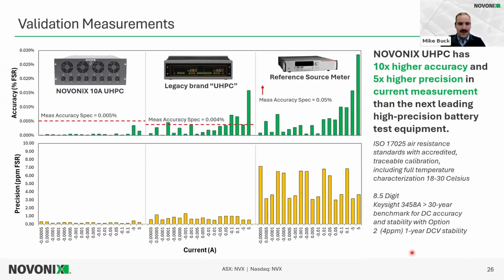Next slide. So basically what it came down to is we determined that the UHPC has 10 times the accuracy, 5 times the precision in our current measurement than the next leading cycler. And to achieve and verify that, we've used traceable resistor standards to the highest precision, as well as a high precision metrology meter on the market that's been the DC voltage standard for 30 plus years, and with the highest specifications possible, purchased to be able to perform at that level. And so as you can see here, this is a chart outlining the different current ranges that we were benchmarking and how we stacked up on precision in the full scale range and accuracy in the full scale range.